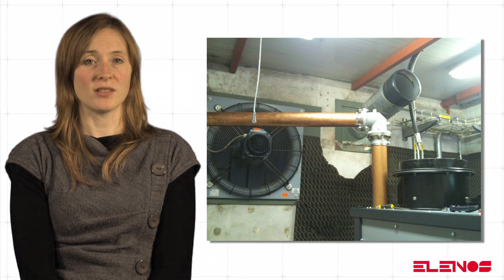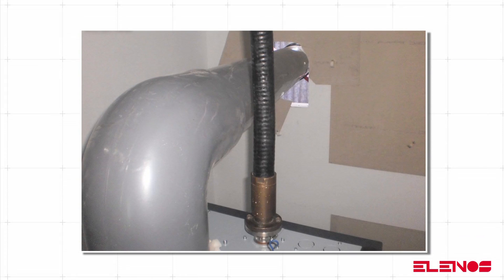The room must be equipped with a system of clean, dust-filtered air ventilation with a flow rate suitable for the equipment characteristics. Outgoing air must be conveyed out of the workstation. If the size or length of the conduit reduces the airflow, additional extraction devices must be installed.